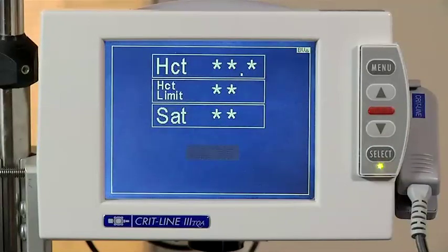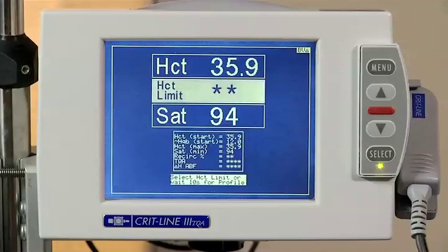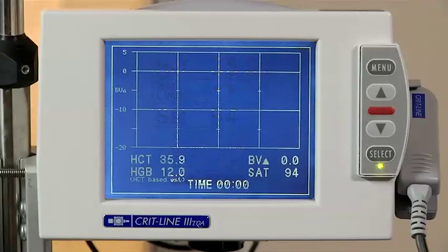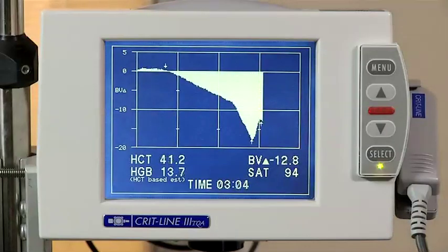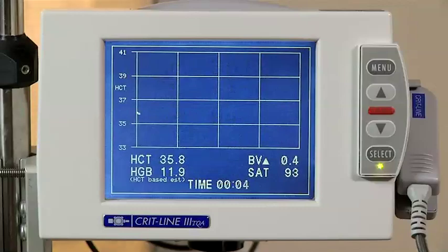It will take approximately 1 minute before any readings are displayed. Once values appear in the hematocrit and SAT fields, the screen will change to the blood volume monitoring profile after approximately 10 seconds. If you know the hematocrit limit of the patient you are monitoring, you can enter it by pressing the up arrow button until the proper number has been entered. When the hematocrit limit is set, the dashed line will appear on the screen.